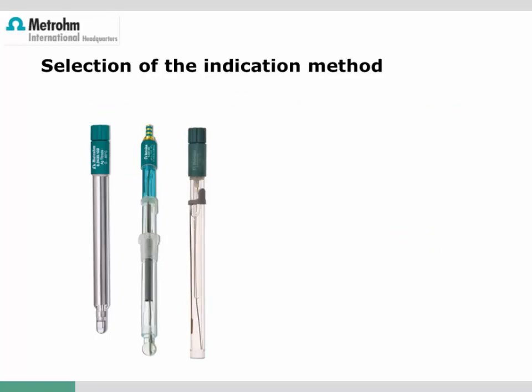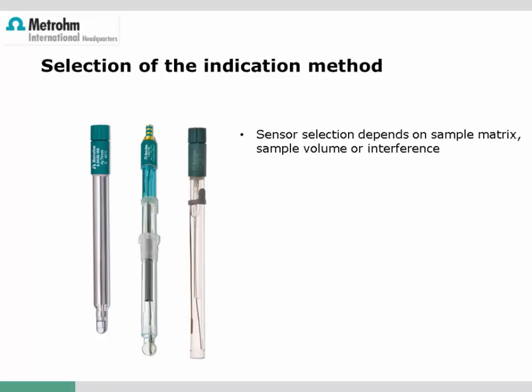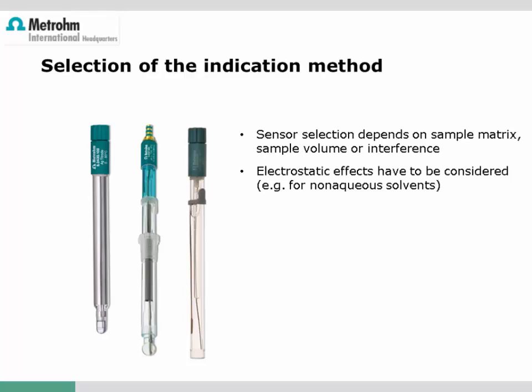Whatever potentiometric indication method is used, the choice of sensor is the most important decision to be made. The sensor selection depends on the sample matrix, the available volume of the sample solution, or any possible chemical interference. Electrostatic effects must also be considered — for example, when non-aqueous solvents are used, the sensor should have internal electrical shielding. The signal change during titration should be sufficient to enable a clear and reproducible endpoint evaluation; as a rule of thumb, the potential jump should be at least 70 mV.